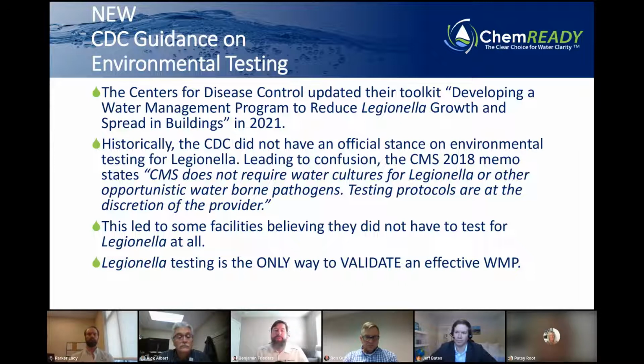Testing protocols are at the discretion of the provider. This led to some facilities believing that per the 2018 memo, they did not have to test for Legionella at all. But if you look at ASHRAE 188, Legionella testing is the only way to validate an effective water management plan.